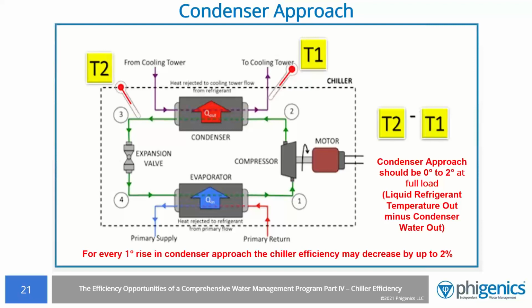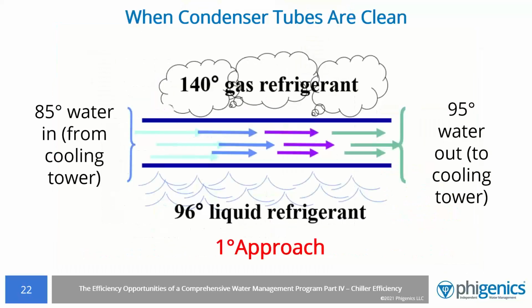The refrigerant is being cooled and changes from a gas to a liquid in the process. The water absorbs that heat in the condenser and carries it to the cooling tower, where it is released into the air. If everything is working the way it should be working, the difference between the two temperatures should be less than 2 degrees at full load. This means the heat is being transferred efficiently. So let's get Larry to explain in a little bit more detail for us what's going on.